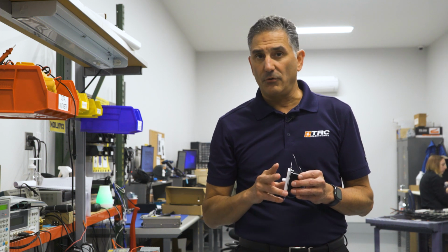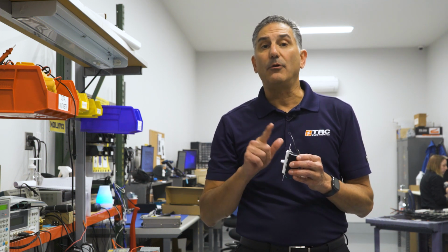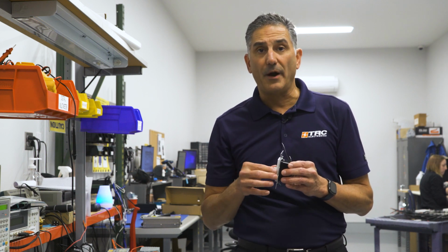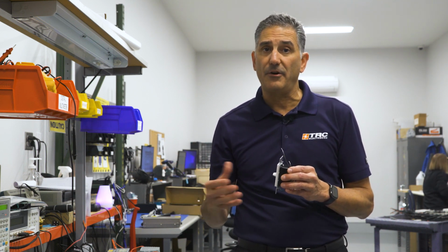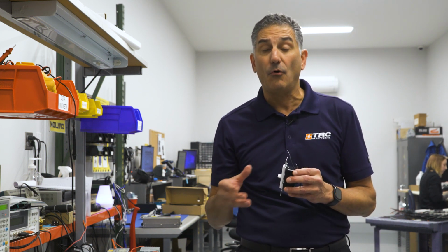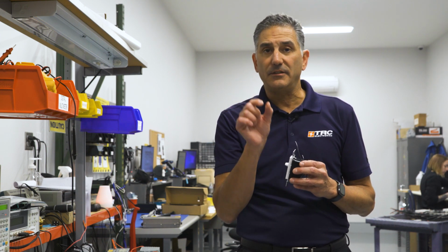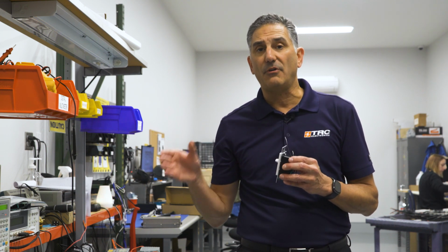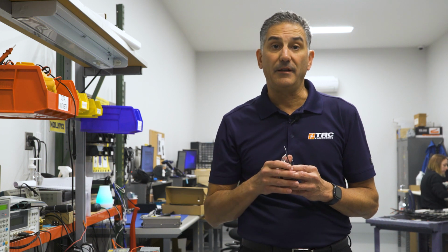Now, a 1 to 10 volt dimmer, when the setting is at its lowest point, it means that there will be 1 volt on the dimming wires, and the driver will then produce usually around 10% light output or 10% current. And then finally, we have what's known as the PWM dimmer, or pulse width modulation dimmer. What that dimmer does is it sets a different pulse width, which tells the driver to actually function with a specific percentage of output current to the LED fixture.